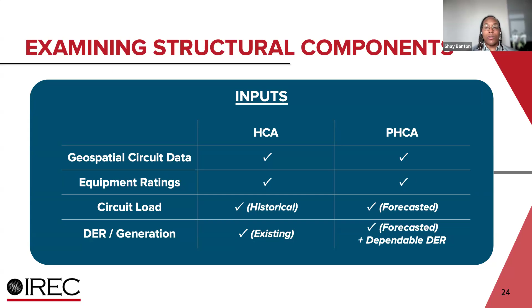Looking towards the evaluations and assumptions, these are like the structural component of hosting capacity analysis - the analysis part of the hosting capacity analysis. Under an HCA, when we look at voltage screens, you have a pretty broad range of analyses conducted. For voltage, you have over/under voltage conditions, rapid voltage change. You may also have some assessments for voltage regulator movements and tap change movements. In PHCA, that's not going to change. You're going to still use those same limits, depending on the standards that you design your systems to accommodate and adhere to. You then have your thermal screens.